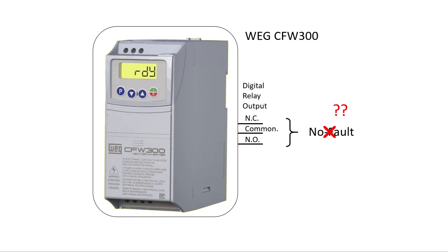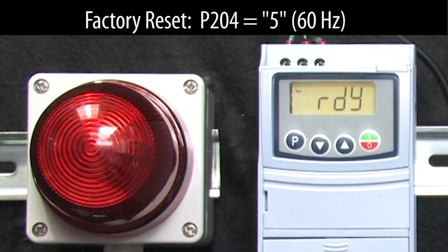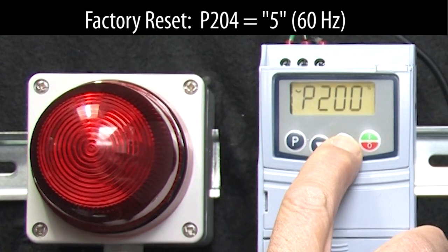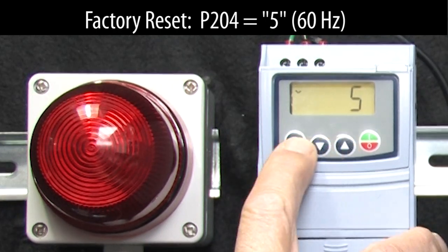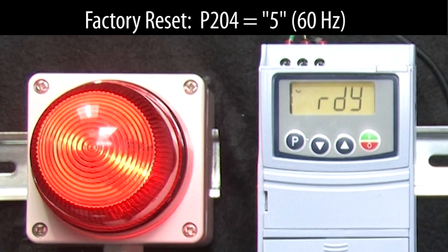Can you change that to indicate something else? Sure. I have an indicator wired into the normally open contact on Digital Relay Output 1 so we can see what the output is doing. Let's do a factory reset so we're starting from a known configuration. And sure enough, the indicator is lit, telling us there is currently no fault — exactly what we expect.